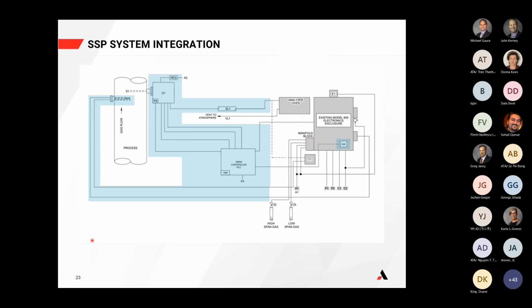It's certainly not developed at this point in time, and I don't really see it operating like an AMEVision, where you would have multiple units. Usually there's not a significant number of high dew point sample points that are close together. So I don't think we've ever thought about the need for that, to be honest. Okay. And I know you guys talked on, Michael and Rod, you both spoke on some of the timing, but can the frequency of the blowback be adjusted, and is instrument air used for purging? Yes and yes. All right.